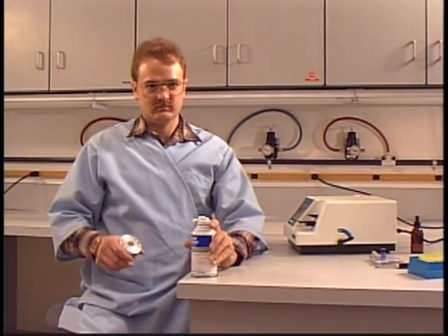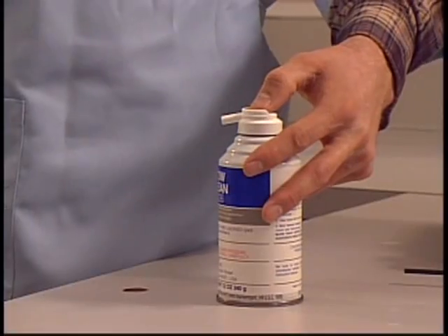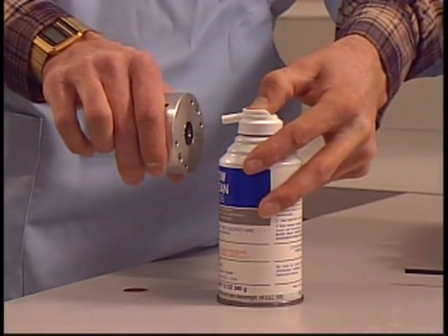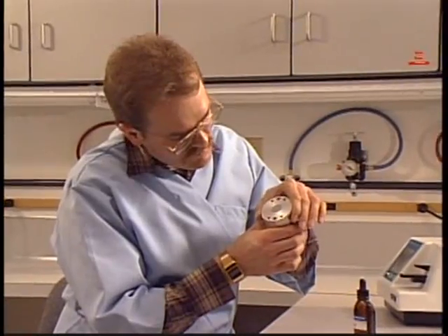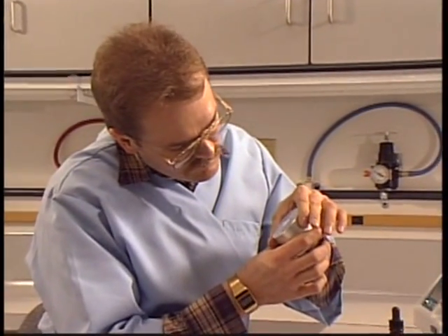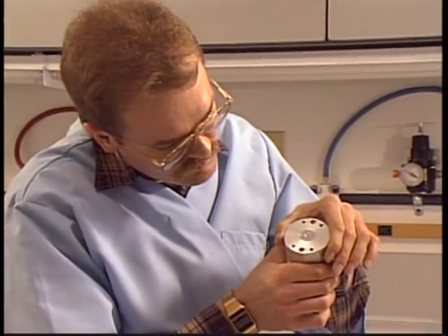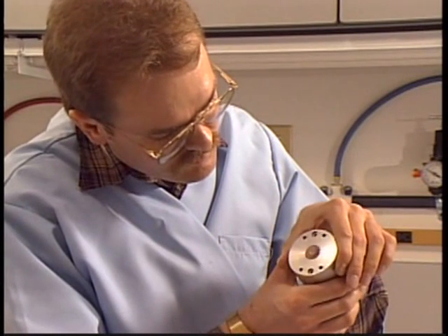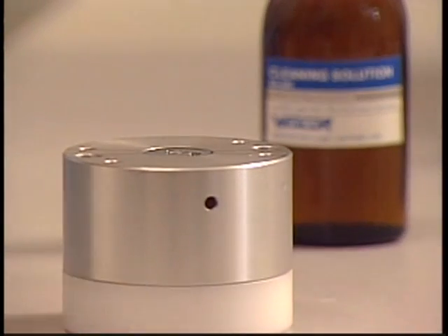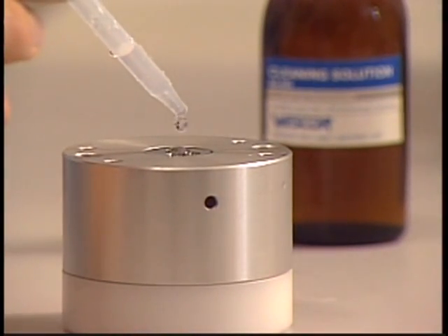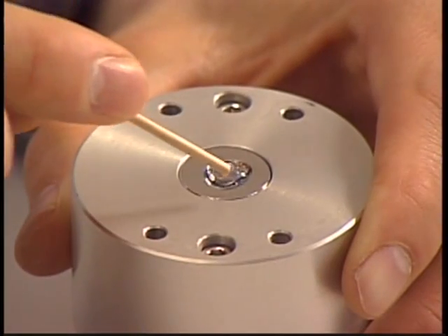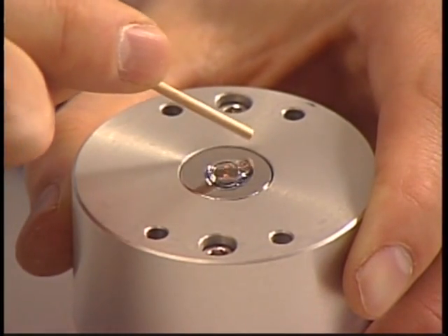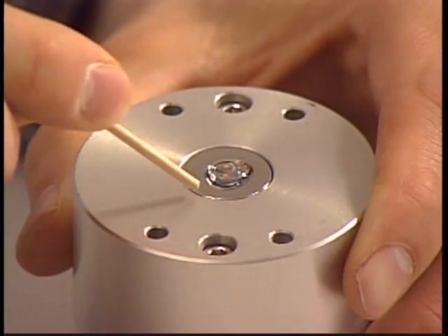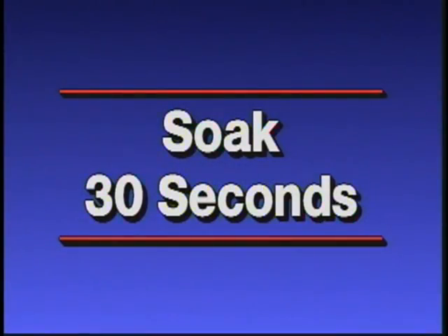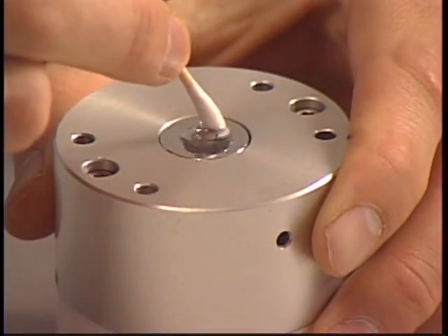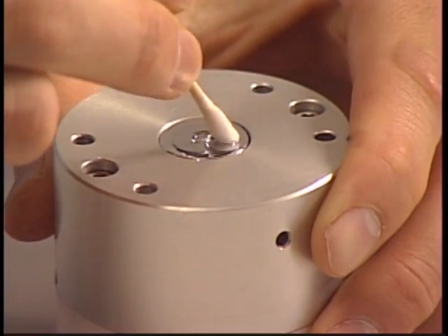Be careful not to bump the can on the thermocouple, but don't worry about blowing the thermocouple away. It can take it. If your thermocouple head still looks dirty or fails the clean test, try using Wescor cleaning solution. Put a drop or 2 of cleaning solution on the thermocouple mount, and just on the mount. Don't let any liquid get in the gap between the thermocouple mount and the body of the head. Let it soak for 30 seconds. Now take a swab and wipe around the mount.